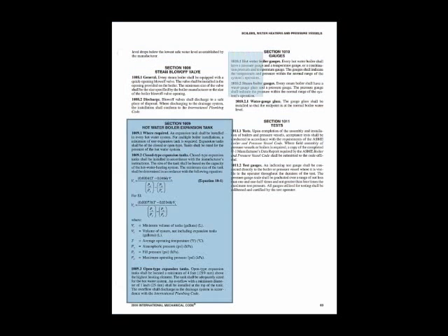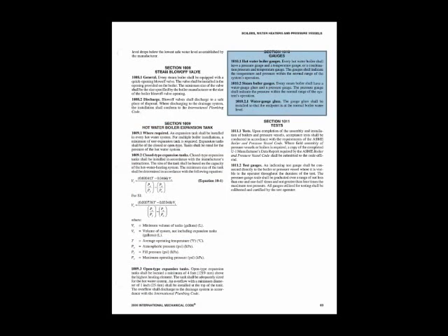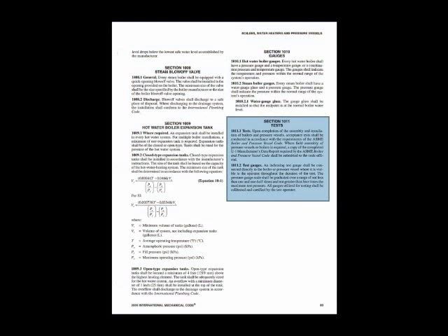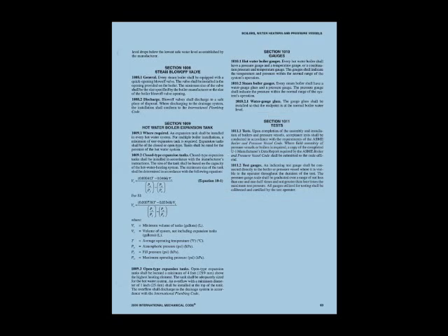You'll see in 1010, all boilers must have some gauges. They have to have a pressure gauge and a temperature gauge. Steam boilers must have a water gauge glass. In other words, you have to be able to visibly see the level of the water in the boiler. You'll notice that 1011 talks about the test requirements of boilers. How high do they have to be tested prior to being put into service? Your building official is going to refer you to this at inspection time.